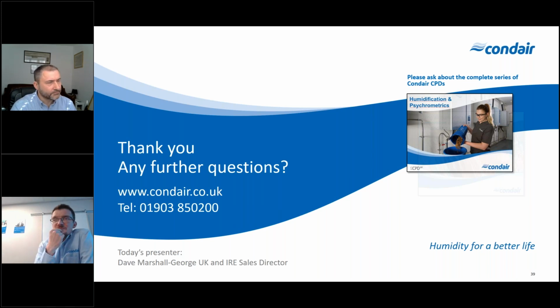I do think it all depends on the type of heat recovery system that you're using and its efficiency, and how much heat you actually want to put onto the fan. Is there really that much of a benefit to heating the air up so much through a heat recovery? In my opinion, the regeneration heater will still be doing most of the heating.